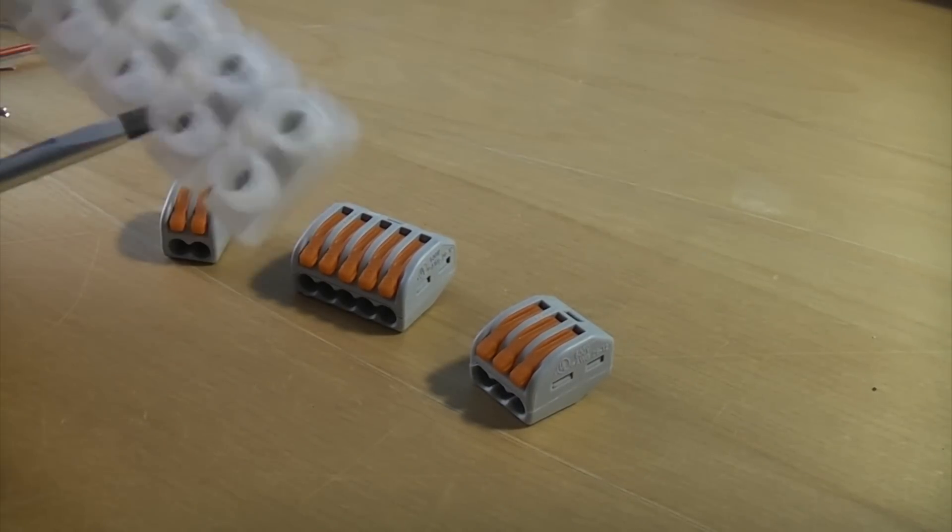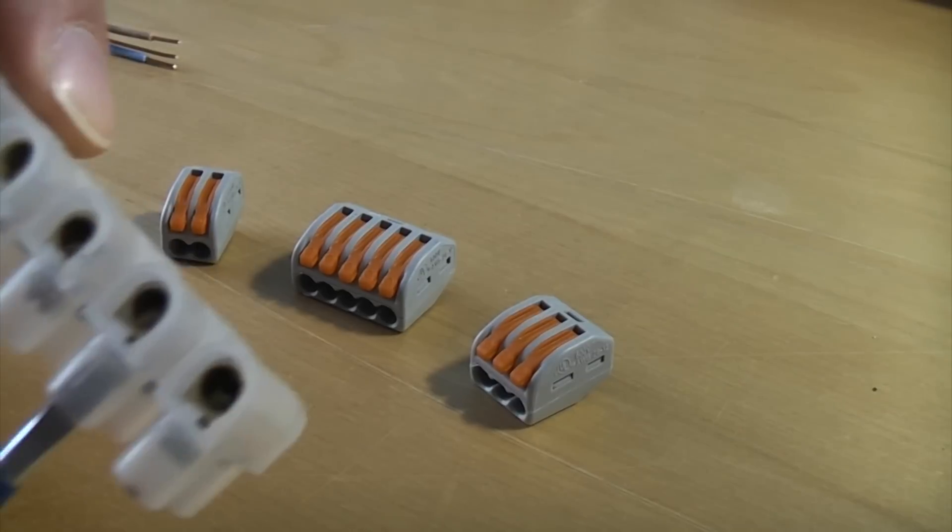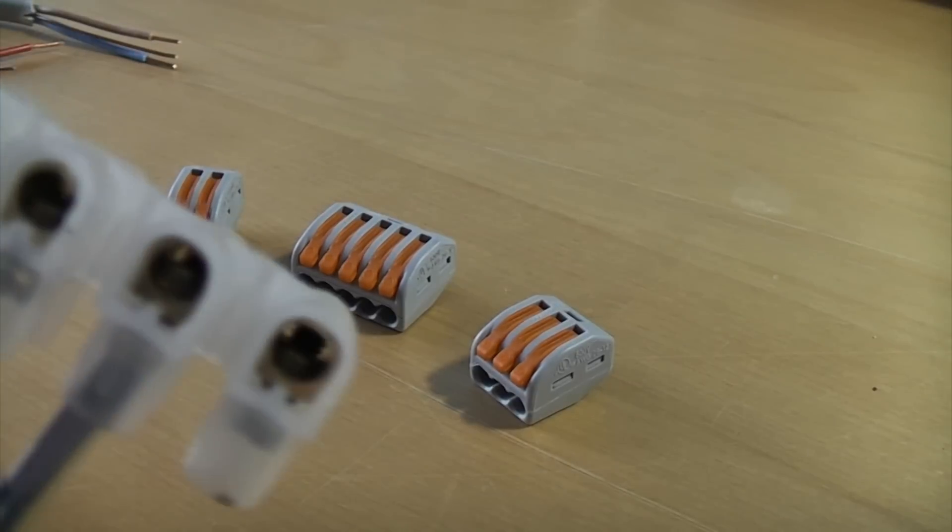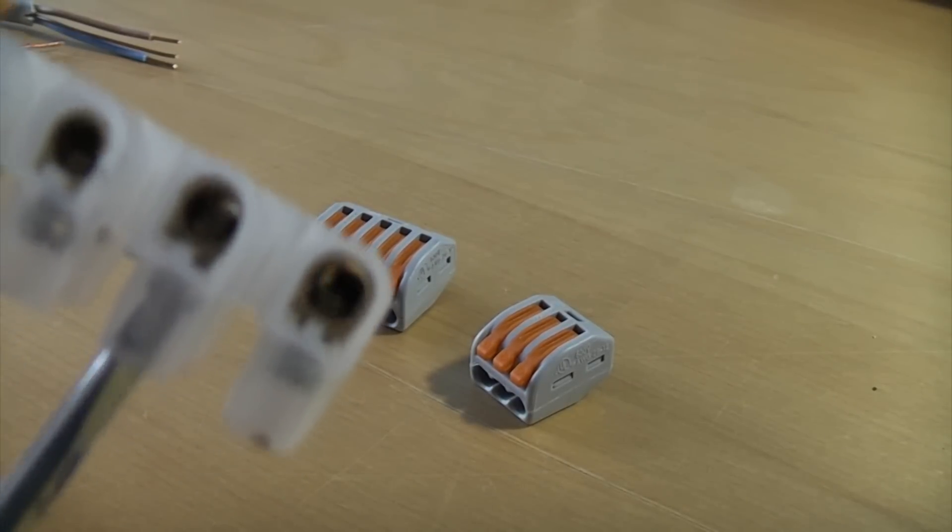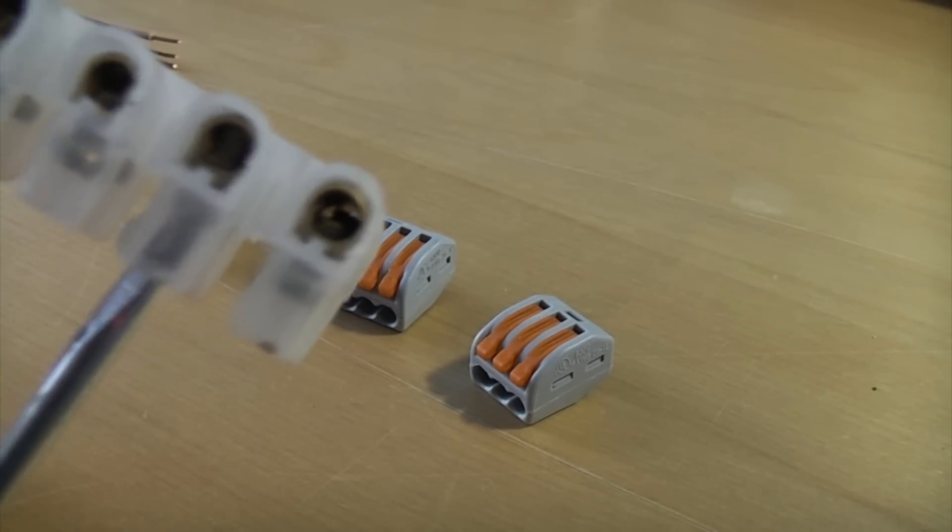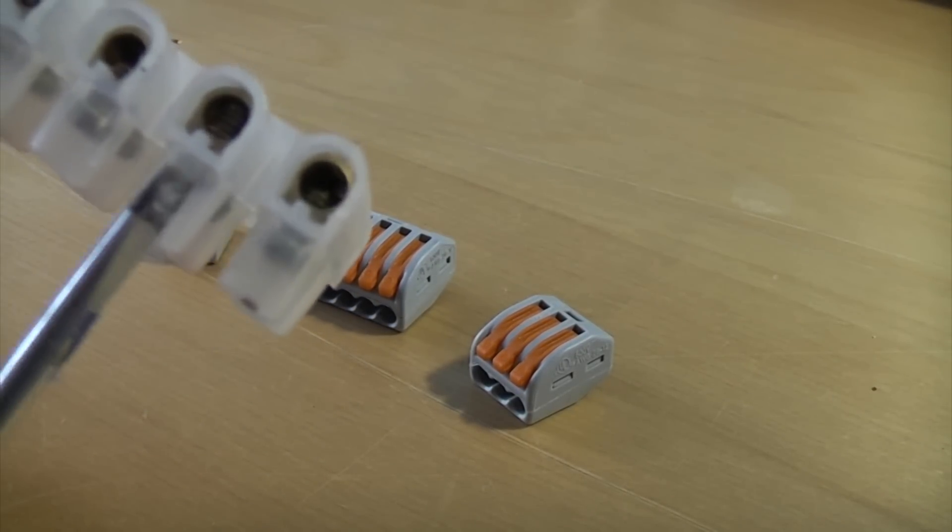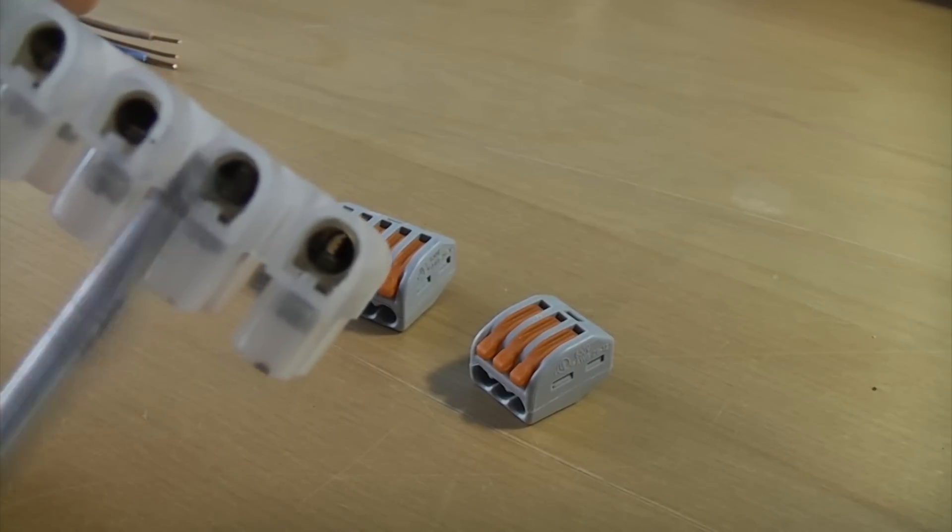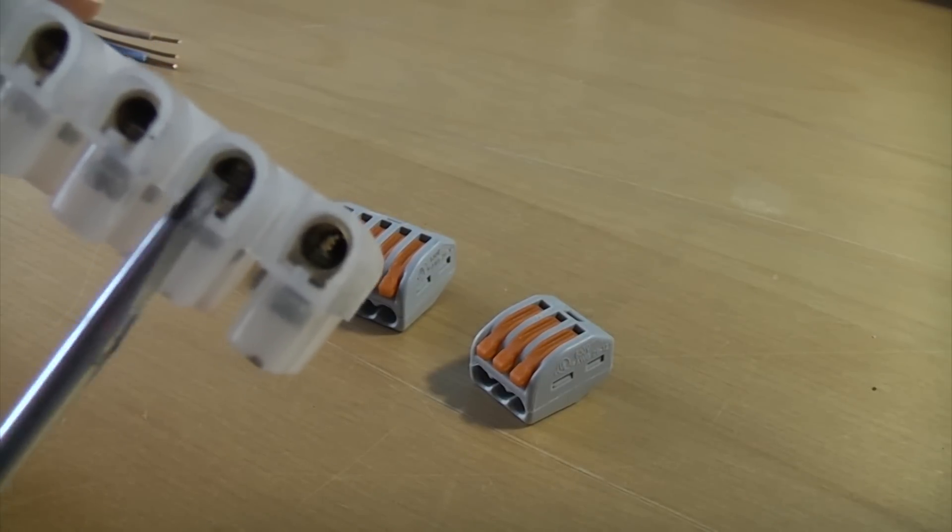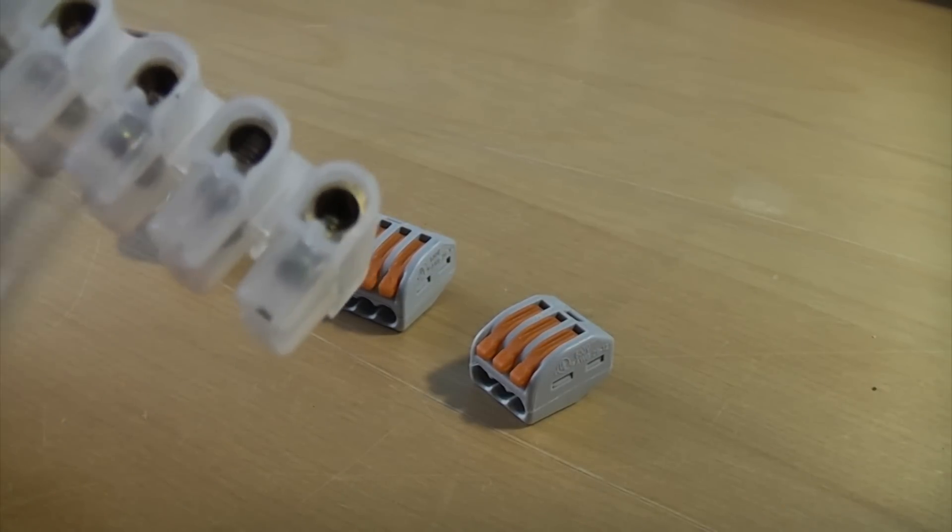Now a big problem with these is that when you tighten the screw up onto the cable, you can actually crush the wire and damage it. Another thing is if you don't tighten the screw up sufficiently, the wires can work loose and then they tend to start sparking, which is dangerous.